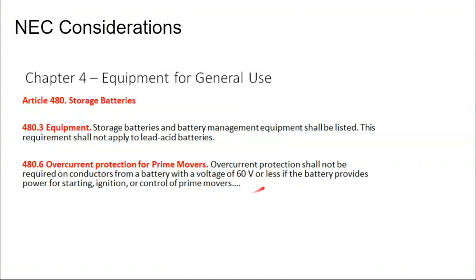So code actually, this is what I would say is the requirement for using new batteries in electric code. It says storage batteries and battery management equipment shall be listed. This requirement shall not apply to lead acid batteries. So this is telling me that, you know, it could be code compliant to use a used forklift battery to power a house, but it would not be code compliant to use a used electric vehicle battery to power a house.